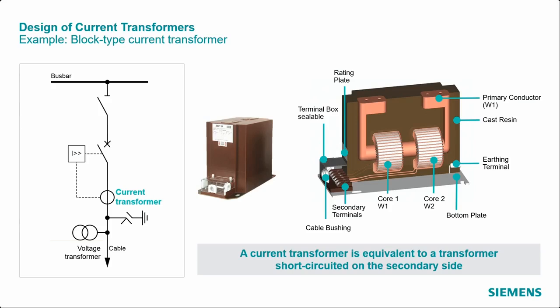It's not more than a U-shaped conductor inside a cast resin housing, which is held by a bottom plate. Around the primary conductor, toroidal cores are fitted. Multiple cores can be used for separate functions such as measurement, protection, and metering, each tailored to specific accuracy and performance requirements. The number of cores varies depending on the application, but typically ranges from 1 to 3 in most designs. The core, typically made from laminated silicon steel, provides a low reluctance path for the magnetic flux generated in the transformer. The current signal of each core is wired to the secondary terminals.